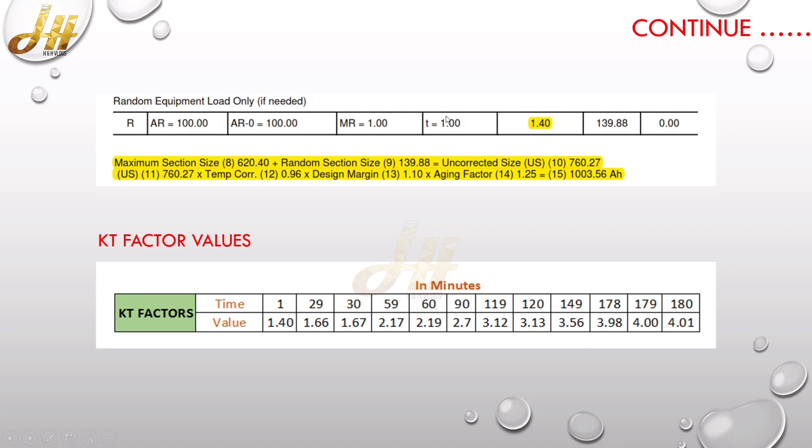So it is mentioned as 100 ampere for one minute. As we discussed, the KT factor value for one minute is 1.40, so we will get 139.88 as the capacity value.